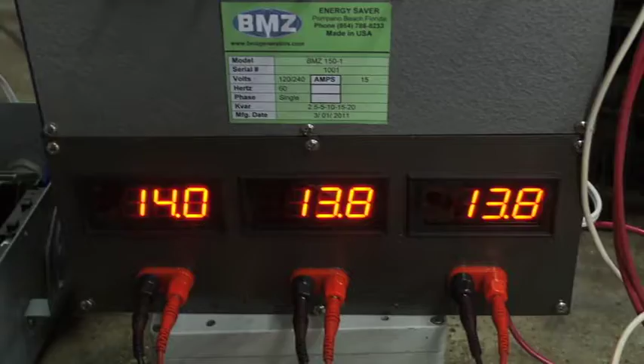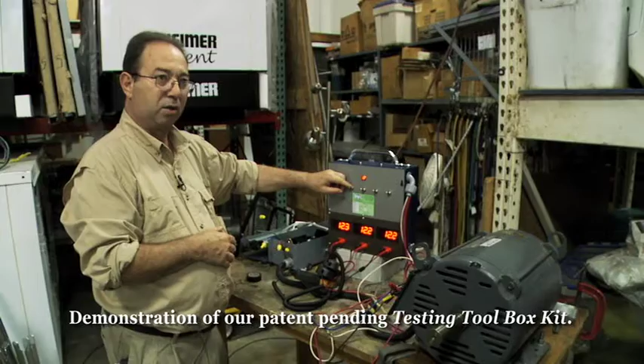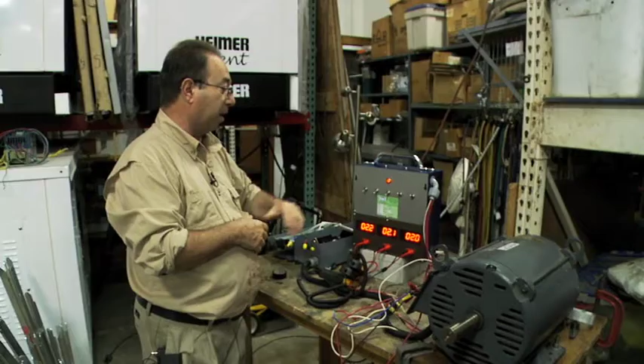It draws around 14 amps. First set of capacitors brings it down to about 12. We put the second set of capacitors in parallel, bringing it down to 9, about 8 to 9 amps. We put in the third set of capacitors, bringing us between 2 to 2.2 amps for each line. If we added another set of capacitors, we'd overdo it—instead of lagging, they'd be leading. This way you're saving on both ends, on starting and on the normal load.